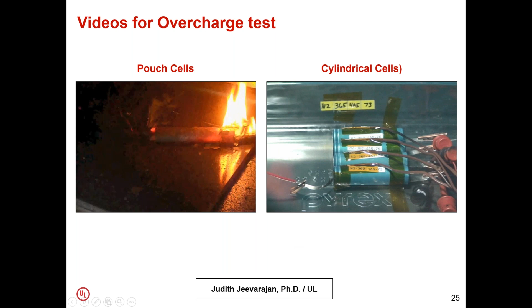So the takeaway here is that battery designs should be fault tolerant to over-voltage and overcharge hazard, and cell level controls do not translate to module or battery level. You have to test in the relevant battery configuration and environment. Cell level monitoring and control should be incorporated into the battery management system. Also, the cell internal protective devices have limitations which you need to understand, and they should not be relied upon unless tested at the right level.